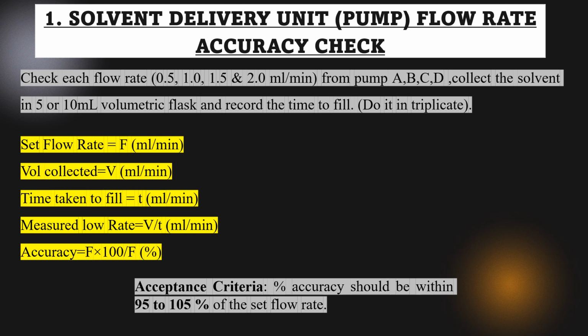You're going to need a volumetric flask, a 5 ml or 10 ml volumetric flask, and a stopwatch. When you start the flow of the instrument and you are collecting the liquid in the volumetric flask, you need to start the stopwatch, and whatever time is taken till the liquid is filled in the volumetric flask up to the mark has to be recorded. What is given here is the set flow rate, like 0.5 ml per minute, and the volume collected, which could be 5 ml or 10 ml, and the time taken that you have recorded on your stopwatch. So the measured flow rate is going to be the volume collected divided by the time taken to fill.